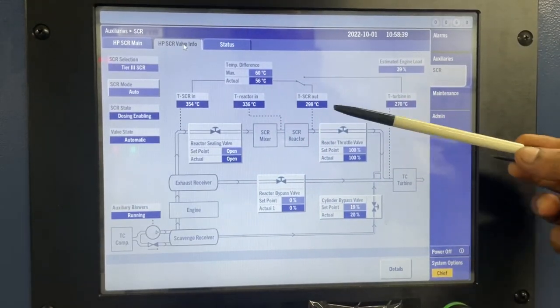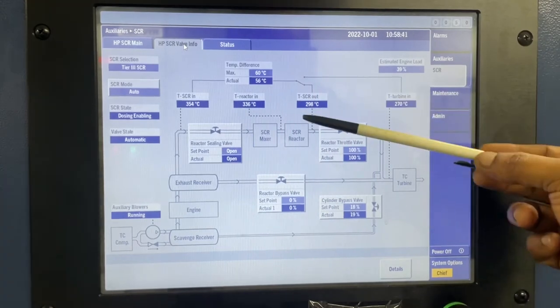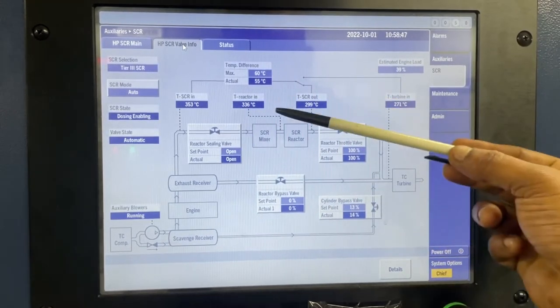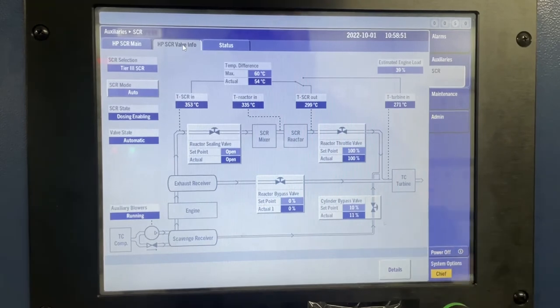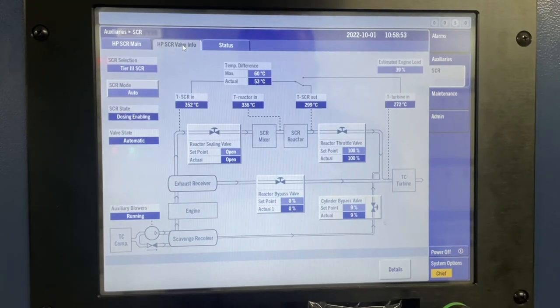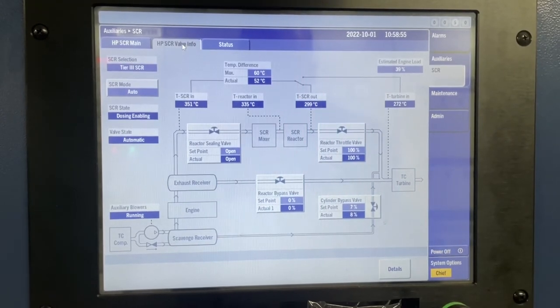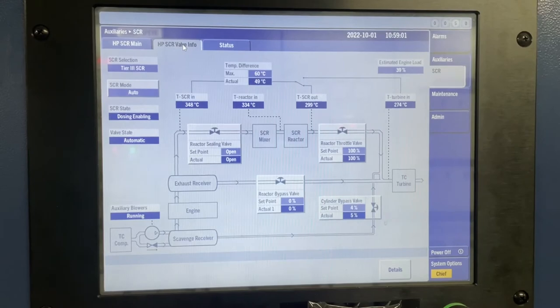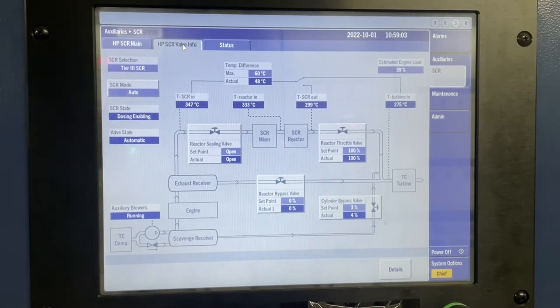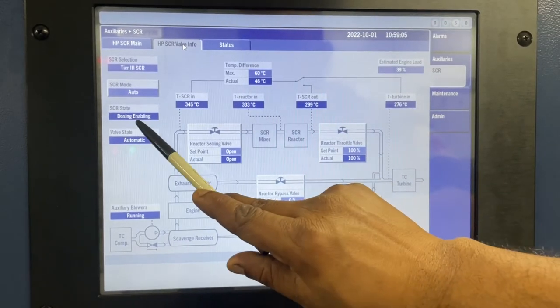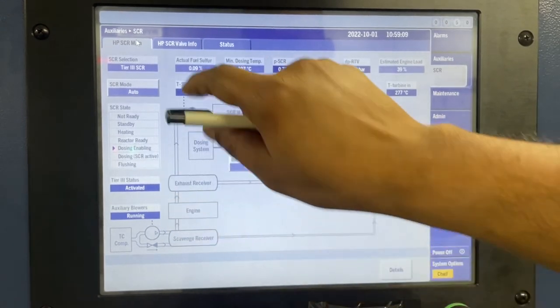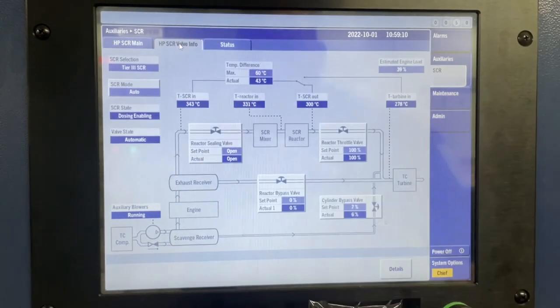Engineers, once the reactor is ready — meaning the reactor outlet temperature has come above the minimum dosing temperature — the CBV starts to close. Then the SCR state will change to dosing enabling. In this period, the urea pump will start.